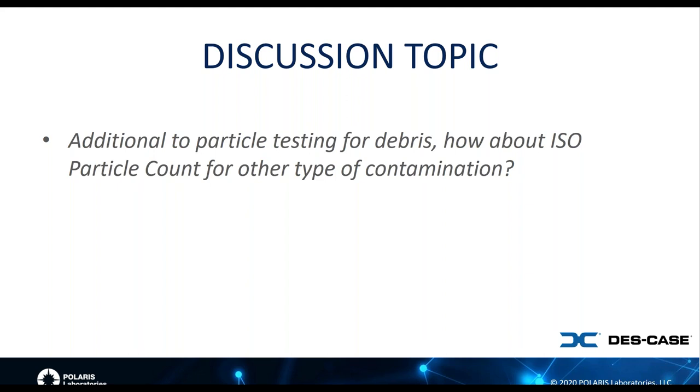So you want to be careful with looking at particle counts from perhaps other sources, because if the lab is not using that method, you can get some false positives. But Bob, I know you use that method in the lab for pretty much every sample. Yeah, I will let Bob talk a little more about that one. But yes, there are several types of particle count procedures that can be run at the lab, at every other lab.